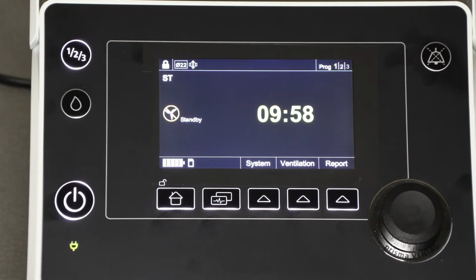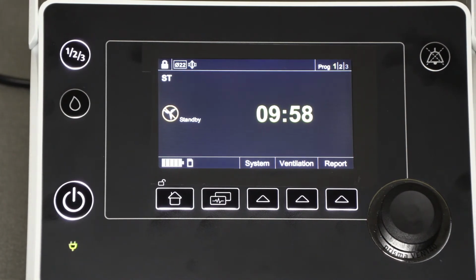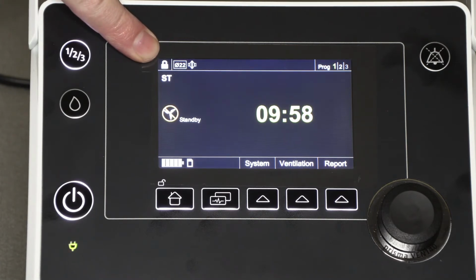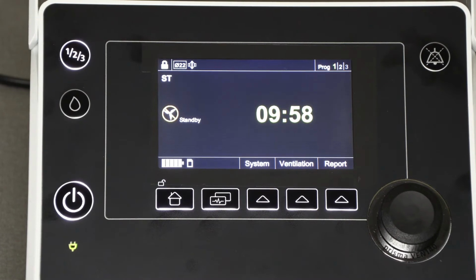Let's look at the various symbols on the screen. Starting at the top left, you'll see the lock symbol. If this is locked, it means that the clinical settings are not accessible. If the symbol shows it is unlocked, then the settings in the clinical menu are available for adjustment.